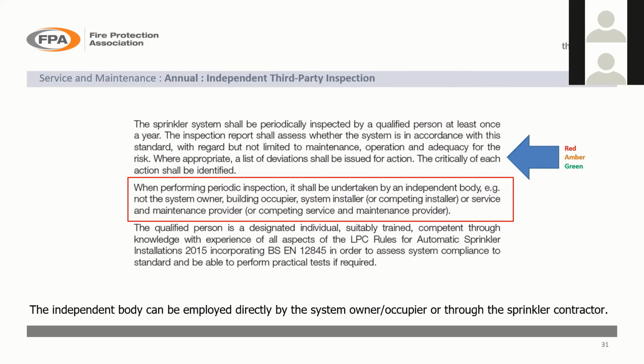The periodic inspection should be undertaken by an independent body. It's not the system owner, it's not the building occupier, not the system installer or a competing installer, or the service and maintenance provider or a competing service and maintenance provider. It's a bit of a mouthful, but the idea is that the inspection is carried out by a completely independent third party who's got no interest other than to make sure that the system complies with the standard, whichever standard that is, which was covered by Dale earlier in the webinar.